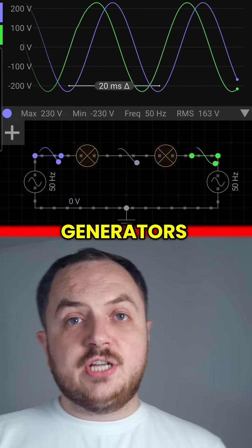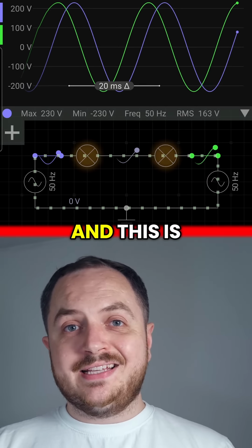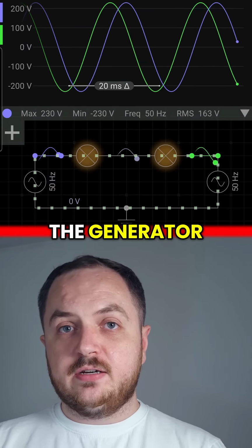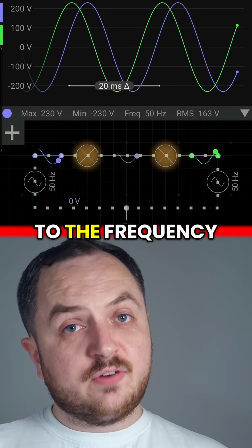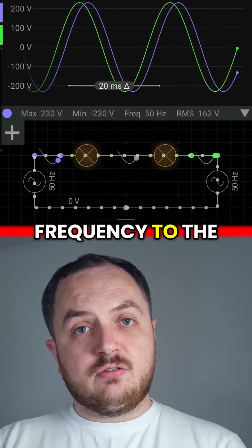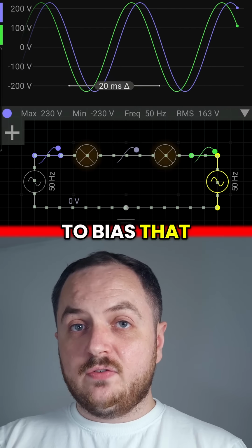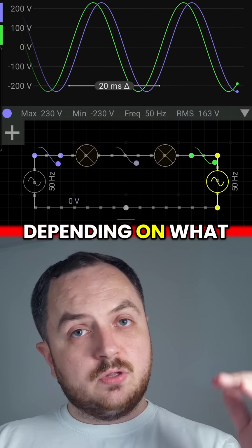For the frequency, generators also have a governor on them, and this is what determines the speed of the generator. The speed is directly proportional to the frequency. So in order to get the frequency to the right level, we just need to bias that governor to go up or down depending on what the main supply is.